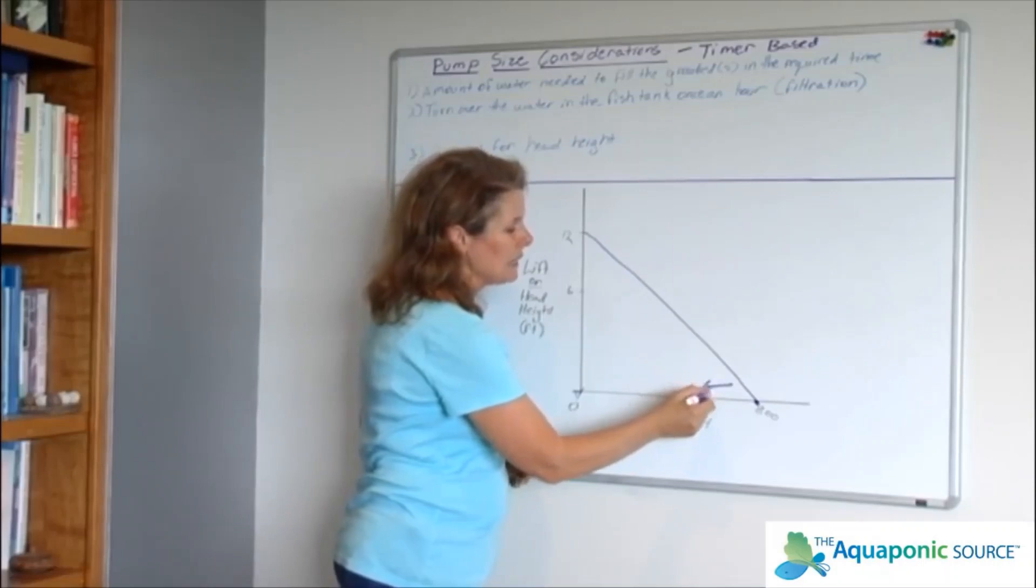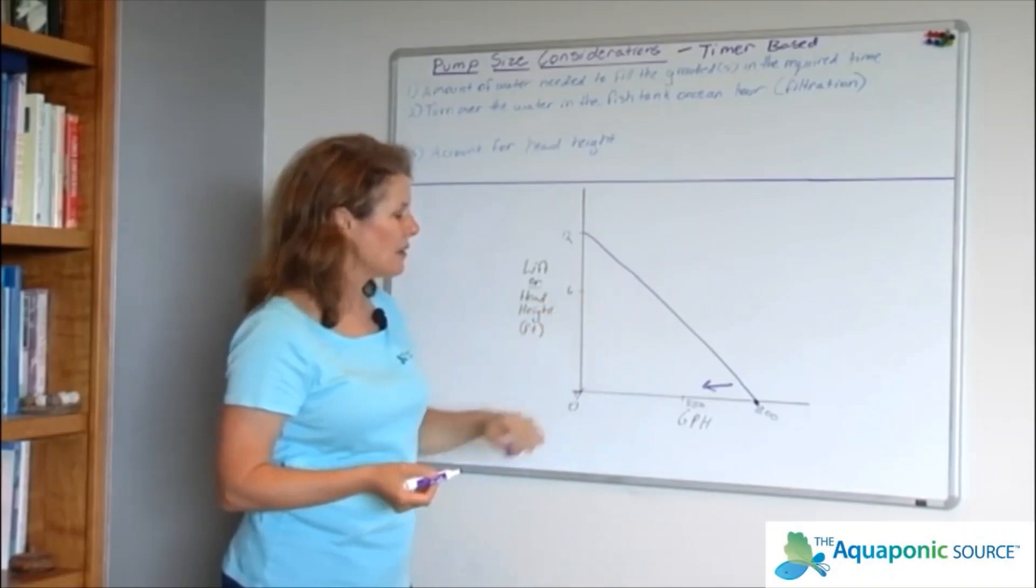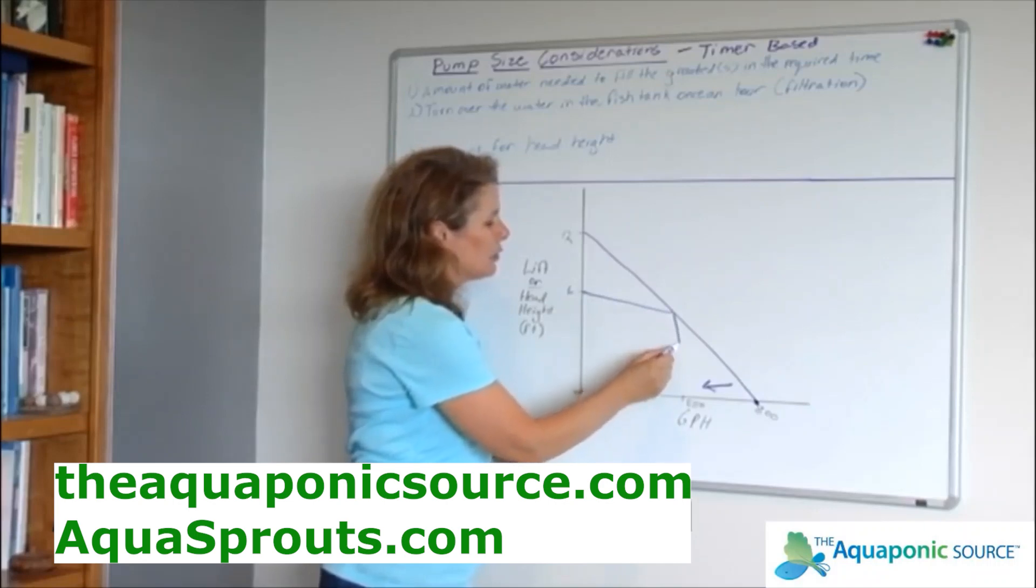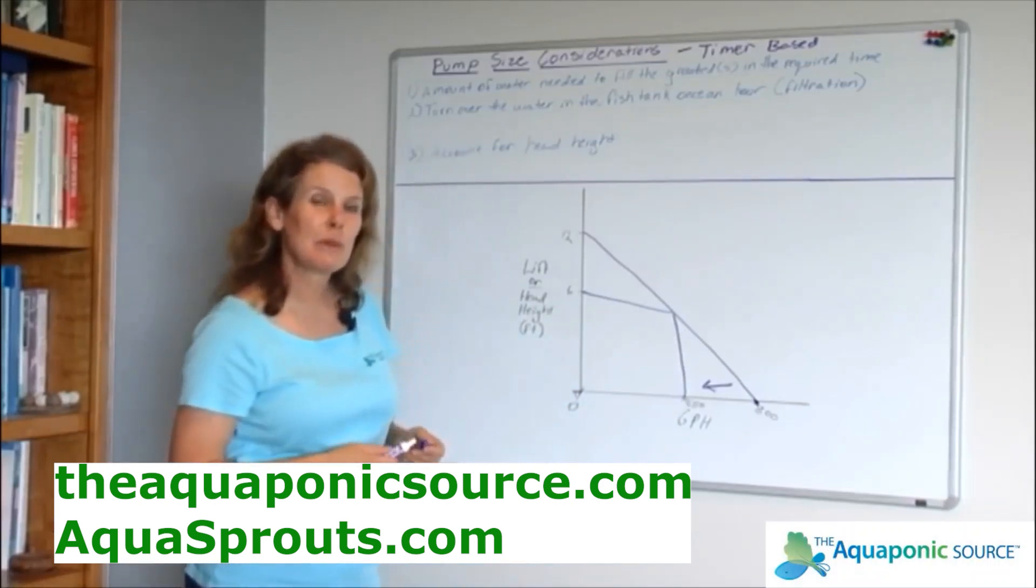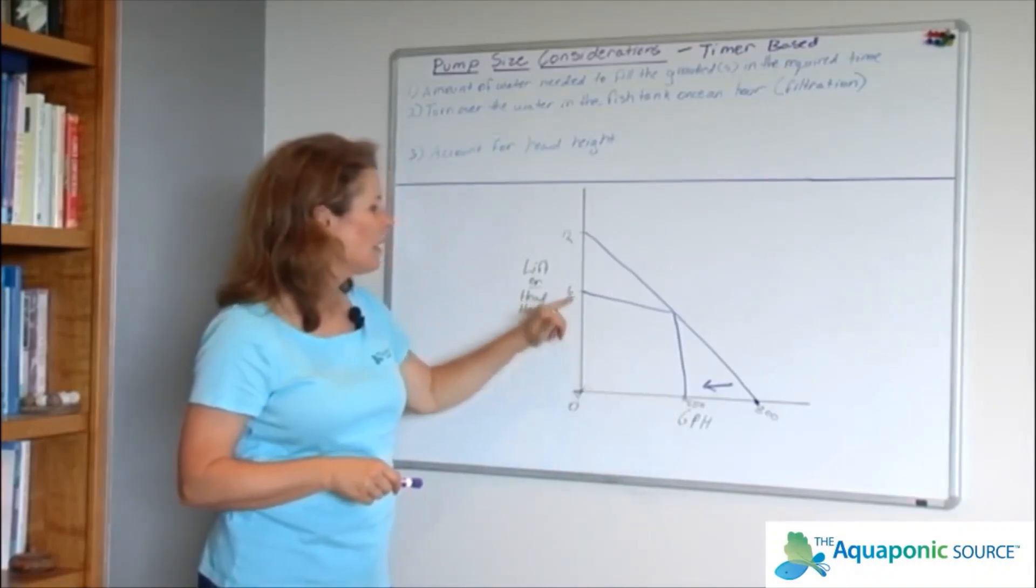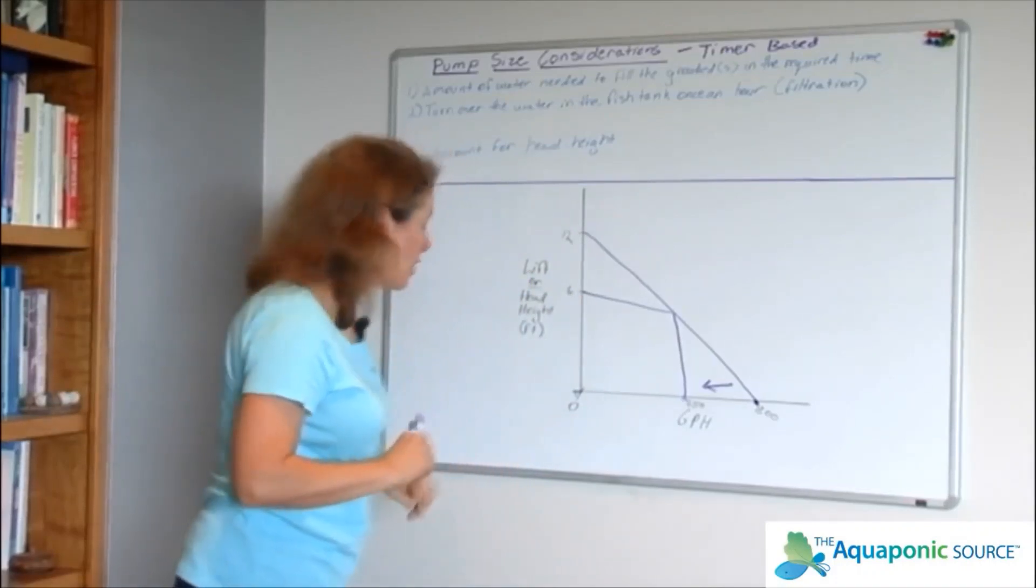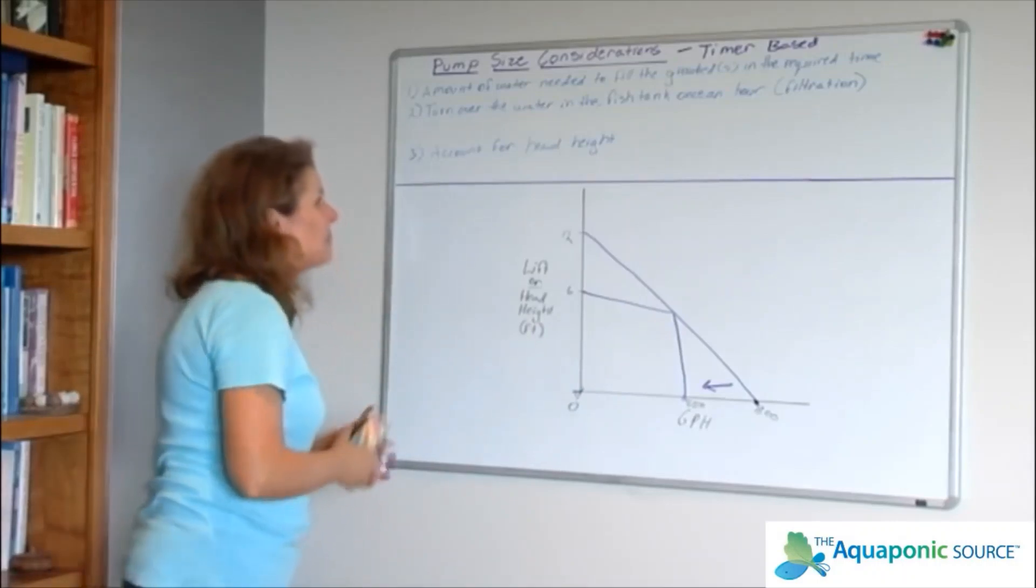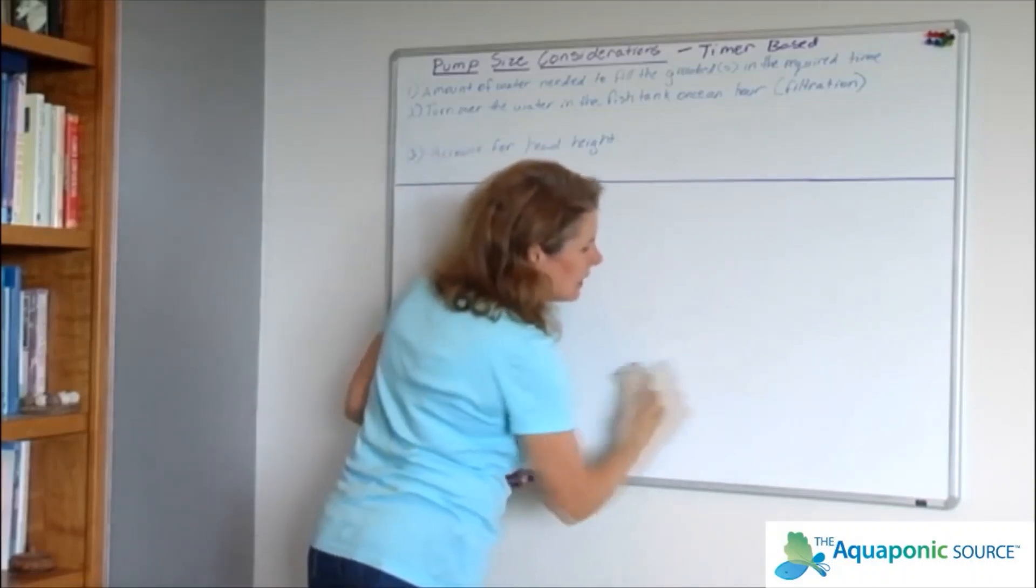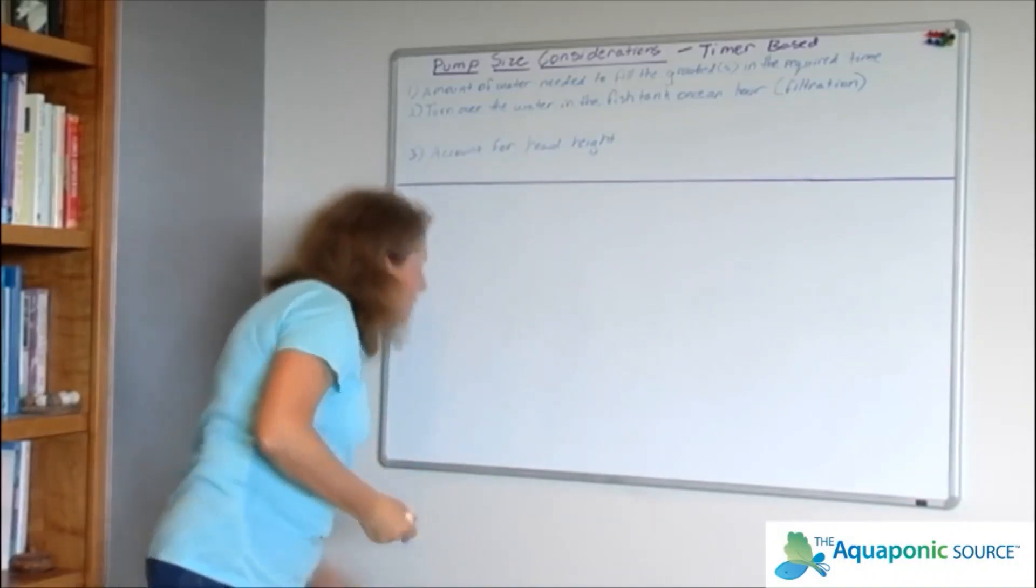This 800 gallon per hour pump starts here at zero lift, and as you go up higher and higher, you see that you're getting less and less performance. In fact, just to get another data point, at six feet of lift it looks like you're only pushing 550 gallons every hour if you're pushing it up to six feet of height. This is a very important thing to know about any pump that you're looking at. Now what I'd like to do is actually take you through an example of how to calculate the pump for a timer based system.